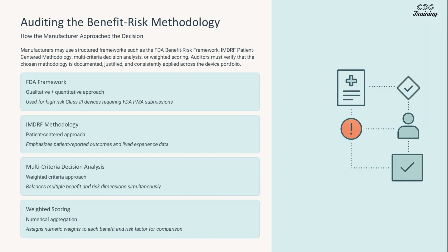Manufacturers may use structured frameworks like the FDA Benefit Risk Framework or IMDRF methodology. Auditors must verify that the chosen methodology is documented, justified, and consistently applied across the device portfolio.